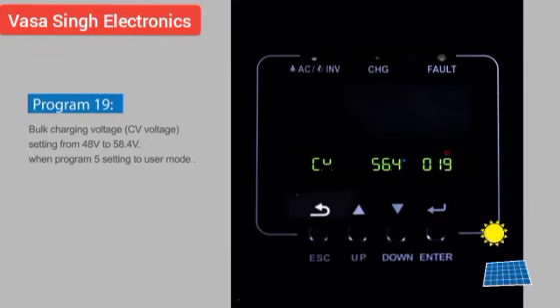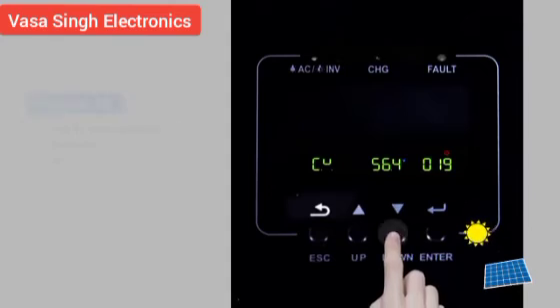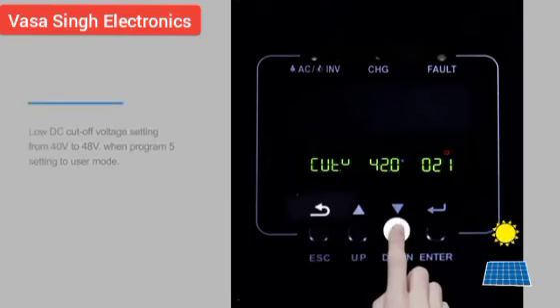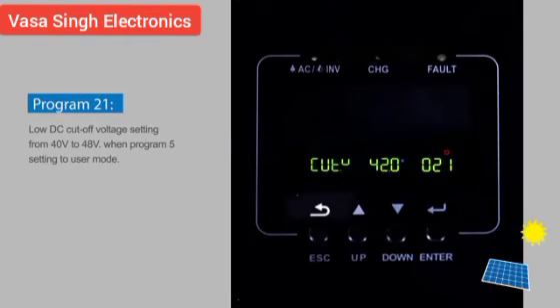Program 19: Bulk charging voltage (CV voltage), adjustable from 48 V to 58.4 V when Program 5 is set to user mode. Program 20: Floating charging voltage, adjustable from 48 V to 58.4 V when Program 5 is set to user mode. Program 21: Low DC cutoff voltage, adjustable from 40 V to 48 V when Program 5 is set to user mode.